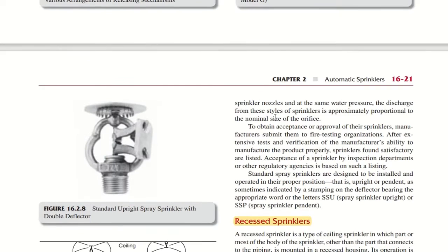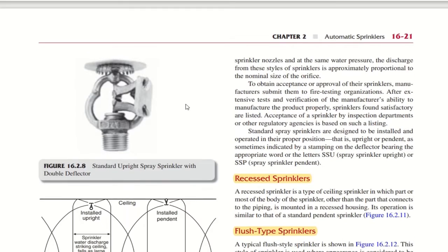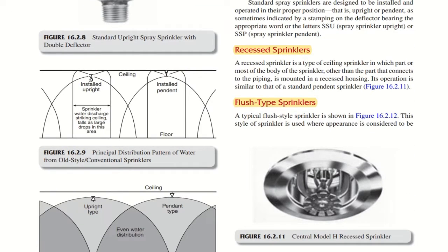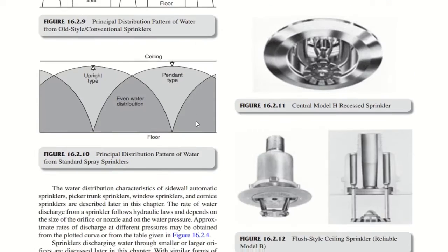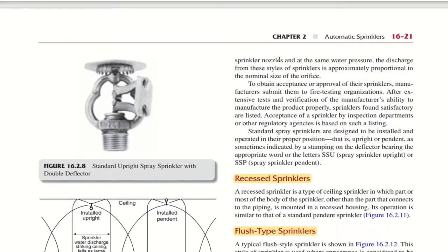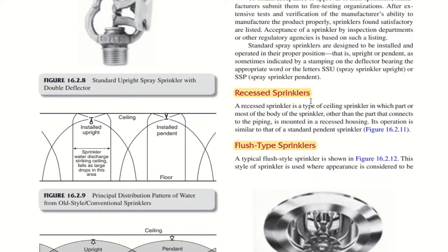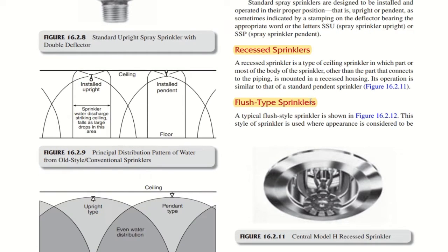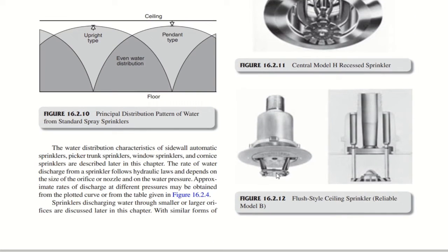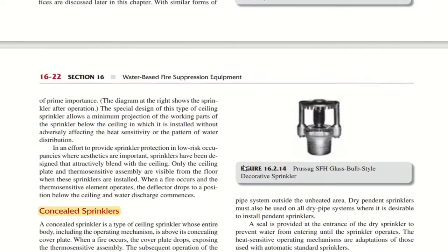Water discharge patterns they have shown in the next slide. Just check here, installed upright. For example, if you install an upright sprinkler below the false ceiling or the roof, the spray pattern will be like this. And a pendant sprinkler, you will install in the ceiling, so the spray pattern will be in this way. Just go through the spray patterns as well. So here recessed sprinklers, you have different types of sprinklers. In pendant you have some plate, so these are called flush type plates. You have various types of sprinkler cover plates.